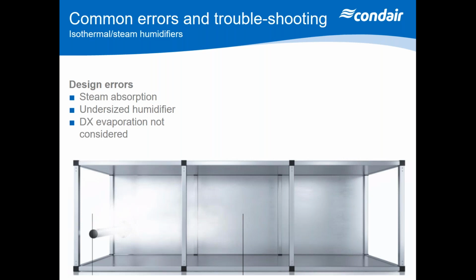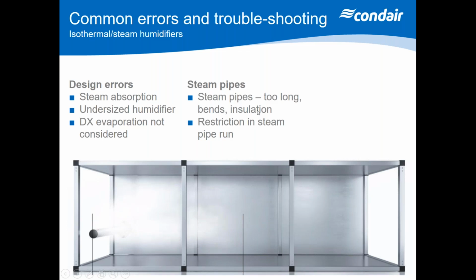Also, you're going to see with small rooms, if people haven't accounted for a DX evaporation, so you might have a split system in your room that's working on a certain amount of sensible cooling and latent cooling. Now, if that coil on that system is running all year round, that's going to be stripping out moisture all year round, and therefore you've got to allow for that in your application and design.